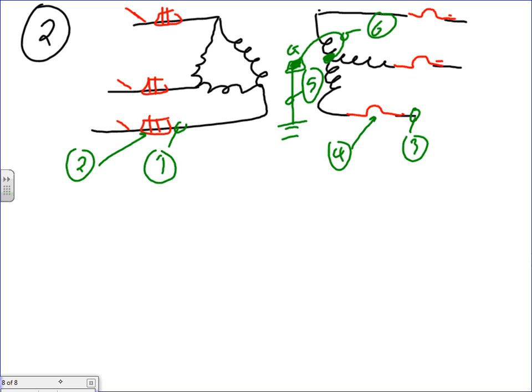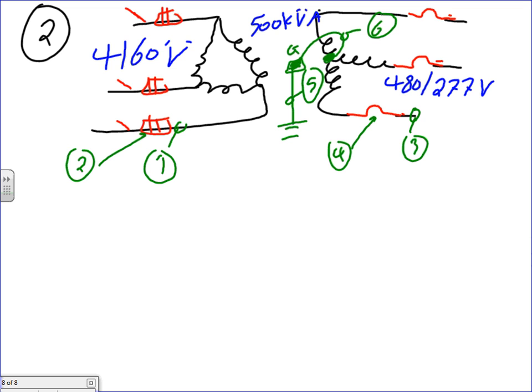The voltage, let's write it in a different color. The voltage here is 4160 volt. 4160. Even here they talk about 4160. And the kVA of this is 500 kVA. And the voltage of this is 480 to 277 volt. And I'm pulling in neutral just to make sure that Mr. Ben is happy. A, B, C, and this is my A and my B and my C.